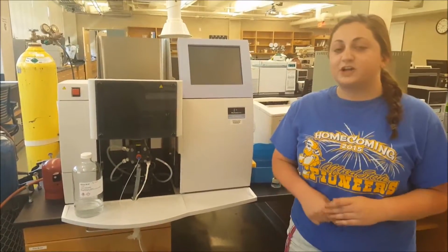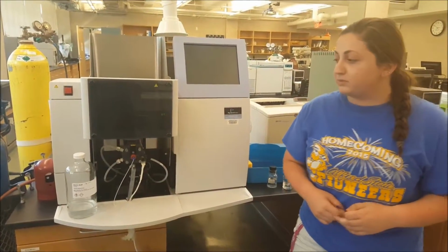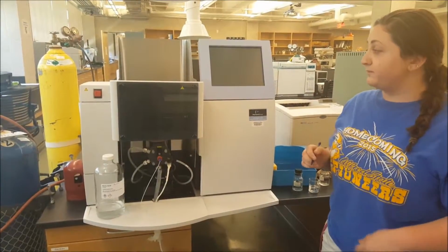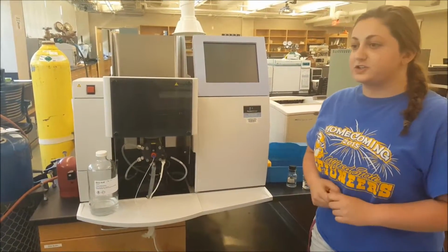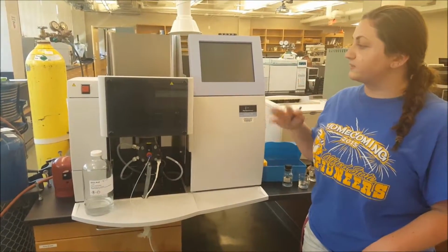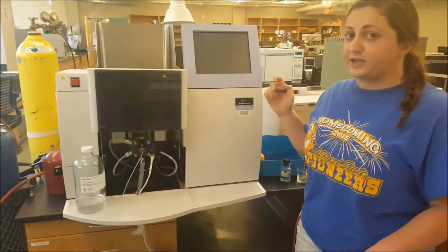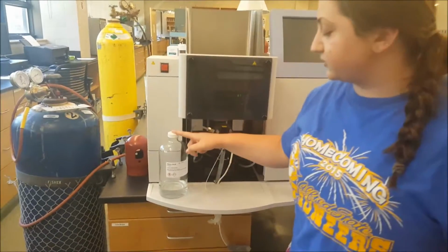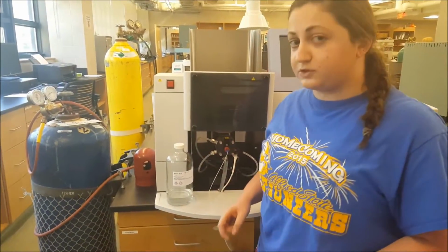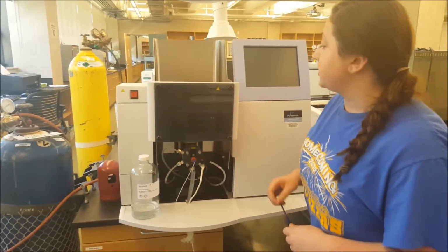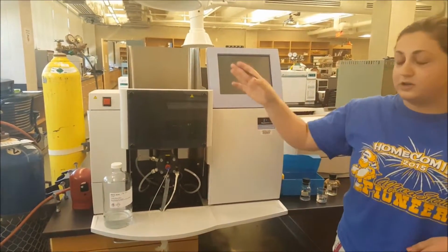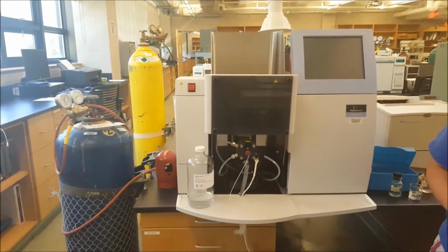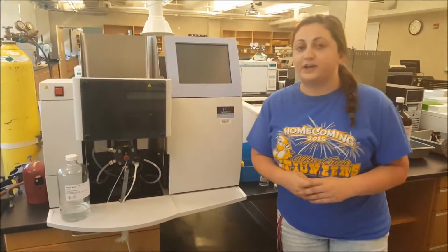Alright, thanks for watching our demo today. Now remember, when you're trying to do this yourself, make sure that you know how to properly use the instrument. Make sure that you set the conditions, wavelength and the slit width, all those things that I showed you today, to their proper conditions. Make sure when using that you also have a lot of solution. The AAS does use a lot of solution. And when you're done, make sure to always turn off the gases and always make sure to bleed the gases as I showed you. And thank you for watching, and I hope that you learned something.